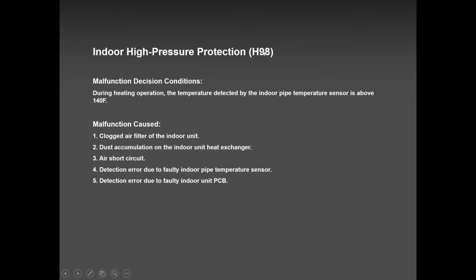Indoor high pressure protection, H98. This error is very common. It exists, but it will not shut down the system. As you can see here, it's a protection. So how does it happen? When you are in heat mode, the indoor unit becomes the condenser and the outdoor unit becomes the evaporator. So let's say you are working on a multi-zone, and if it was a 5-zone, for example, out of the 5 units you are running only 1 unit. So that pressure becomes too large for that little indoor unit. So it will run, and after some time it will trip. It will shut down and come back on again. So in my opinion, if you have a 5-zone and you're running 1 unit only, I would strongly advise you to turn on the other units, but keep the temperature low so that they can absorb some of the pressure of that outdoor unit.